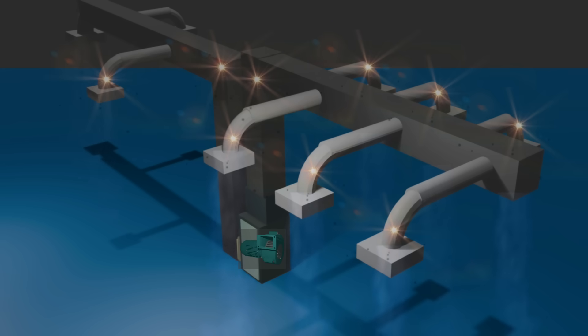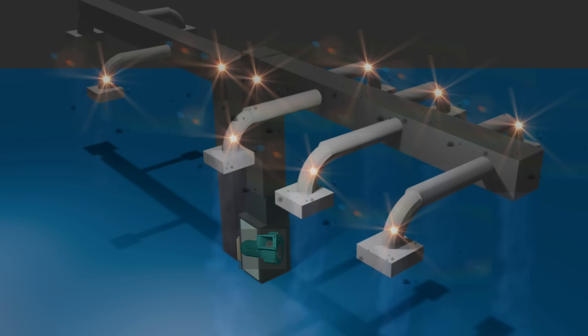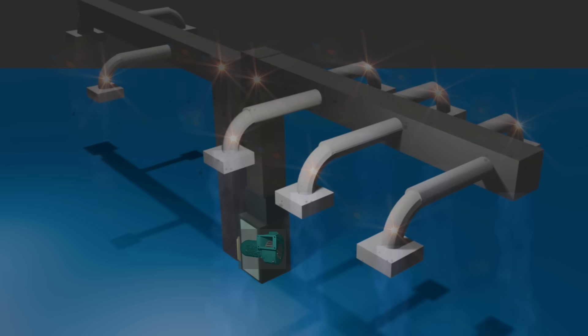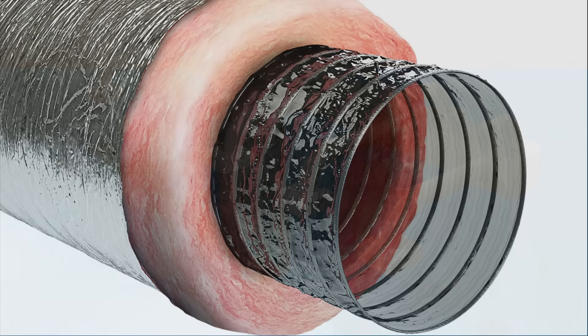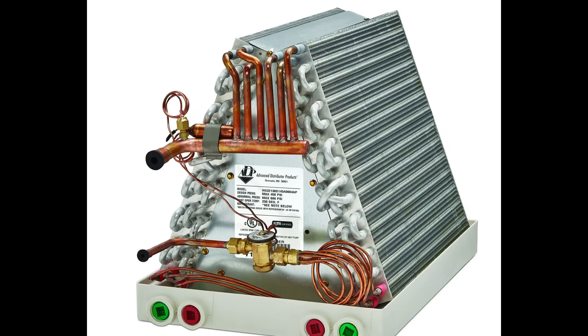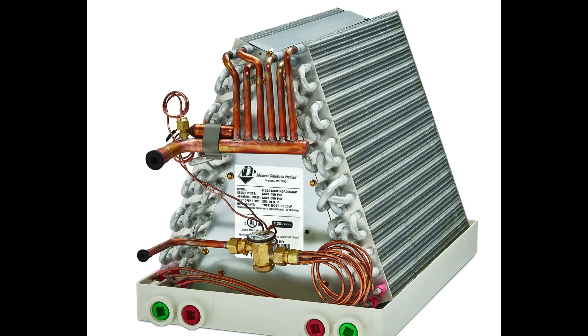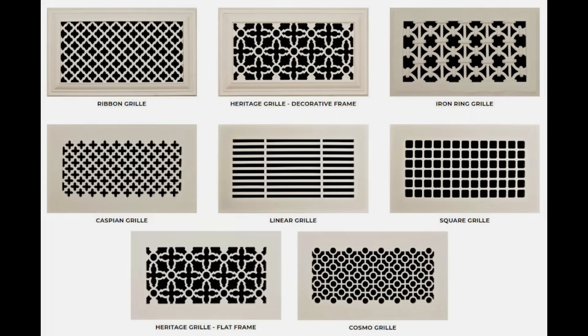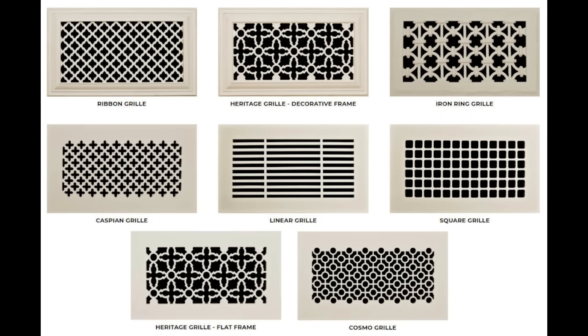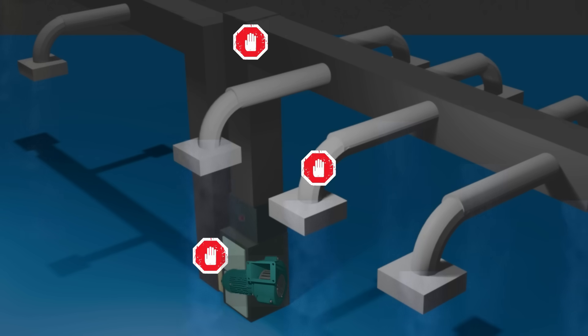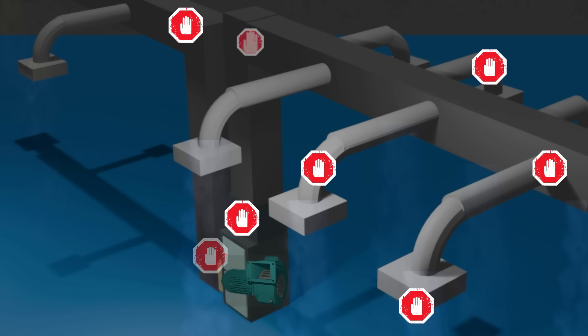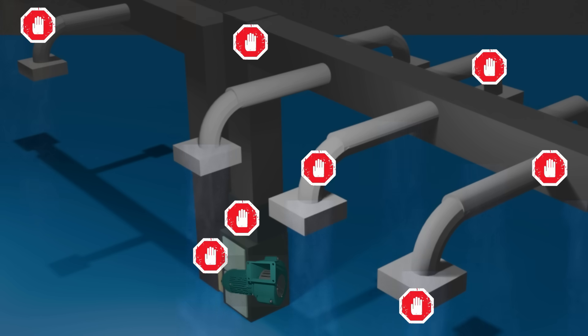Every bend in ductwork is a change in direction the air is forced to take — that's resistance. The spiral lining inside flex duct creates drag — that's also resistance. The air filter, the tightly packed fins of even a clean evaporator coil, even the supply and return grills on the wall or ceiling — these are all obstacles the blower has to work against to constantly move the volume of air required to take command of the space we're trying to condition.